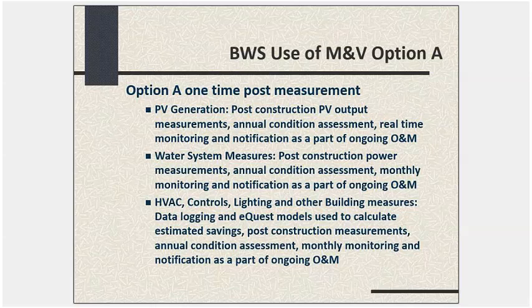But these are good examples of how you might put together a combination of spot measurements, annual condition assessments, and monthly monitoring, at least in the case of the water system and the HVAC controls and lighting, to make sure the O&M stuff is on track.